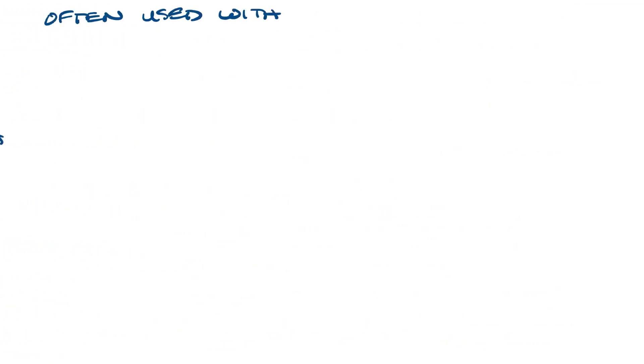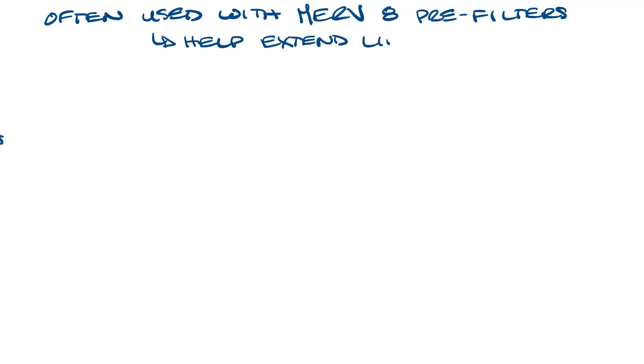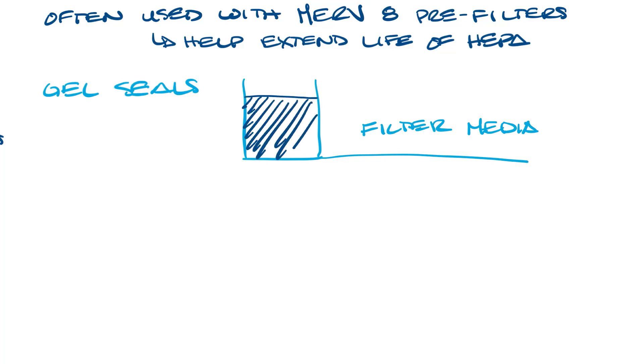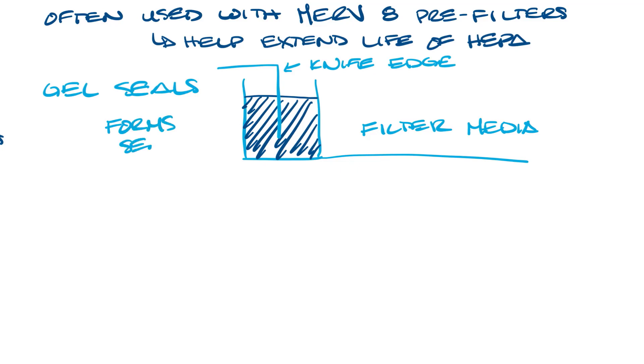HEPA filters are often used with a MERV 8 pre-filter to help extend the life of the more expensive HEPA filter. You will also see gel seals on these filters. The gel seal is a dark blue gel that goes around the edge of the filter, and a knife edge goes into the gel seal forming the seal, making sure no air will leak past the filter media.